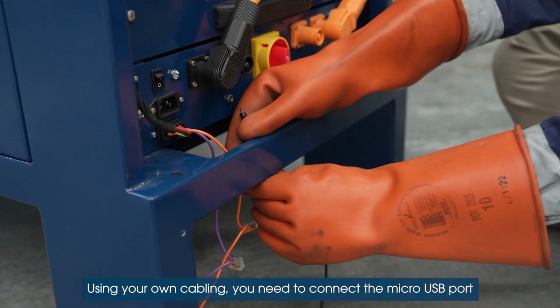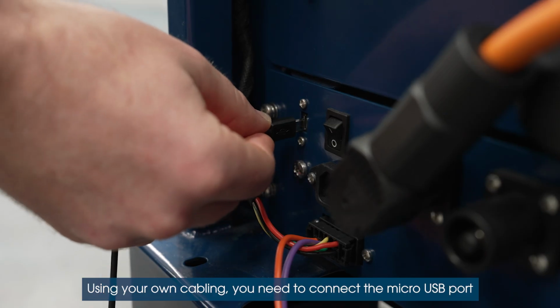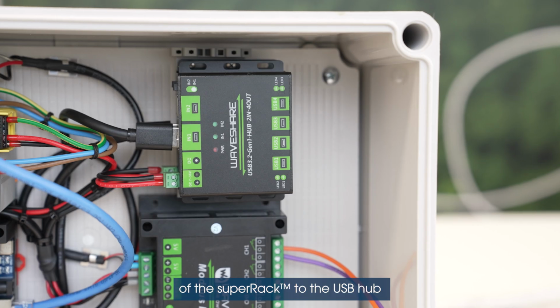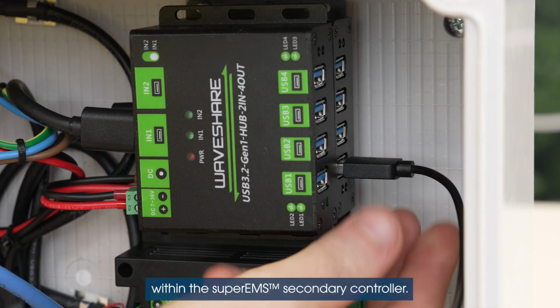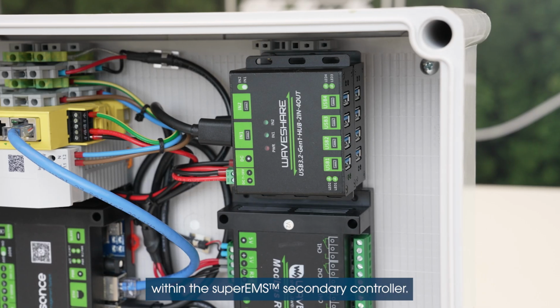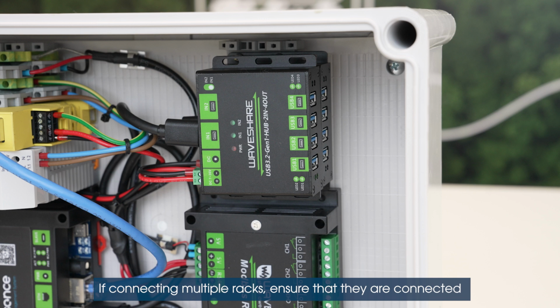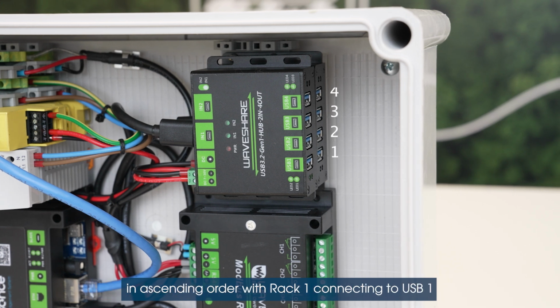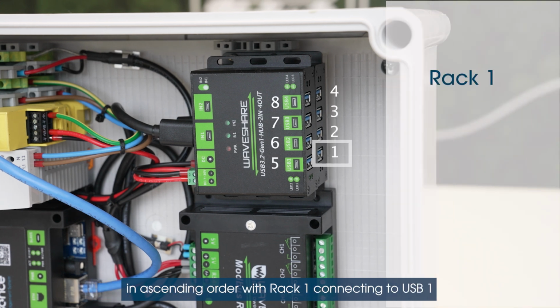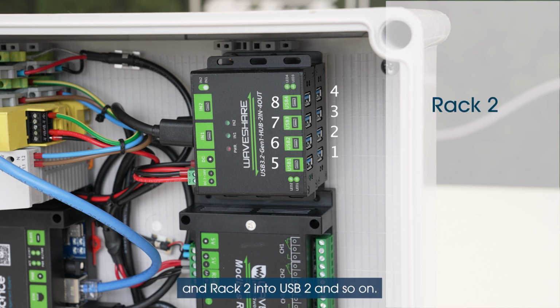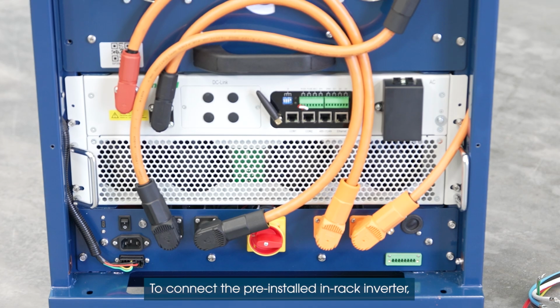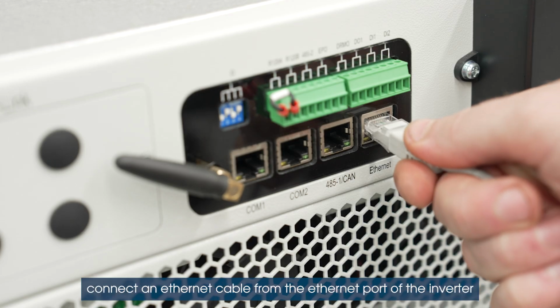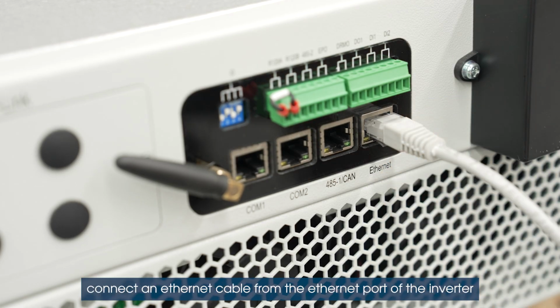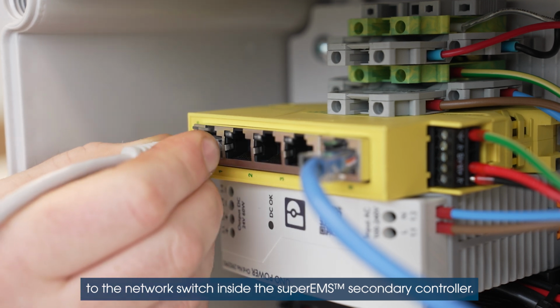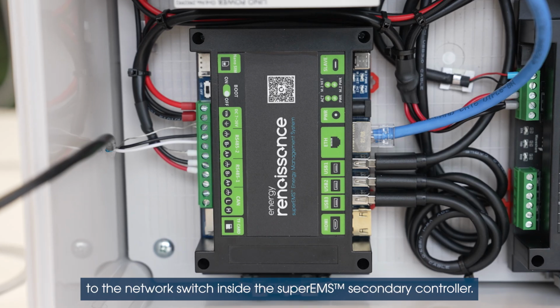Using your own cabling, you need to connect the micro USB port of the superRack to the USB hub within the superEMS secondary controller. If connecting multiple racks, ensure that they are connected in ascending order, with rack 1 connecting to USB 1 and rack 2 into USB 2 and so on. To connect the pre-installed in-rack inverter, connect an Ethernet cable from the Ethernet port of the inverter to the network switch inside the superEMS secondary controller.